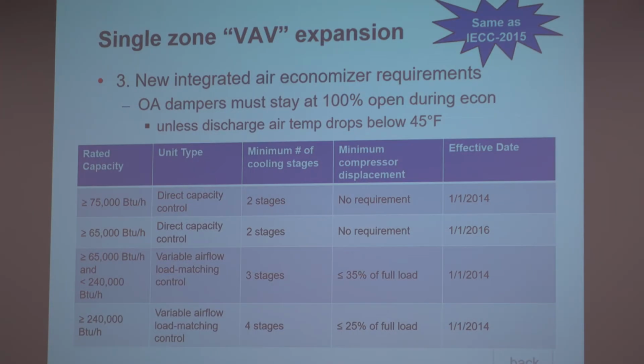So they came up with some of these requirements that effectively changed the design, particularly of unitary packaged equipment, to make it a lot more efficient. And so you have to give credit where it's due to California sometimes, sadly. But the effect of these changes that are really inside the equipment have been far-ranging and really energy-saving. So here's the table for that, and the effective dates are all in the past. So this has to do with what happens when you come out of economizer mode.